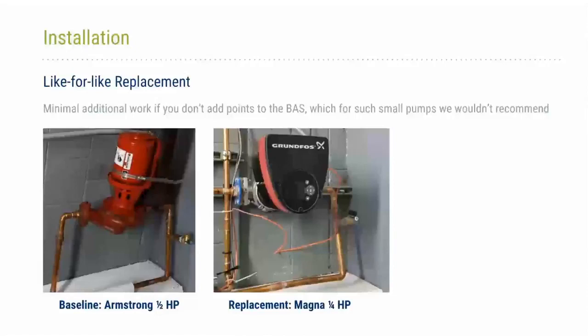Yeah, let me start, and then Tyler can jump in on this one. I think, again, well, I was trying to see if this was domestic hot water pump number 1 or 2. This was domestic hot water pump number 2, but we have to keep in mind that these are the smallest pumps that are manufactured for commercial building applications. You don't get any smaller than kind of 1/4 or 1/2 horsepower. And the water lines are running in that scenario that I mentioned, where you have a very small water line, very high head pressure and very low flow rate on those. So I think the reason the pumps look big is just because these are some of the smaller pumping applications in the buildings.